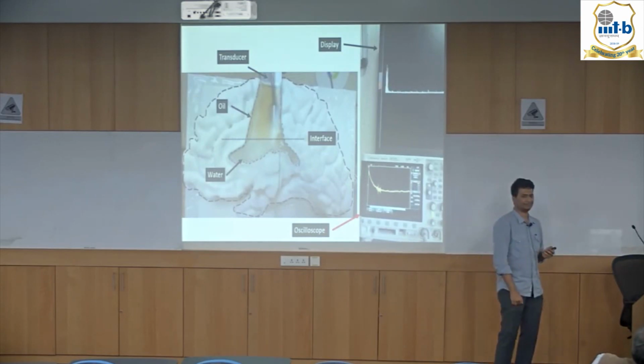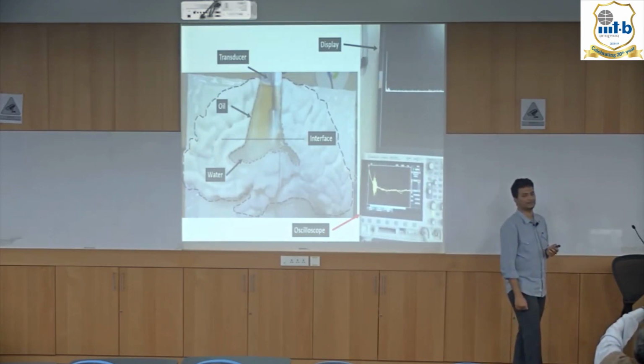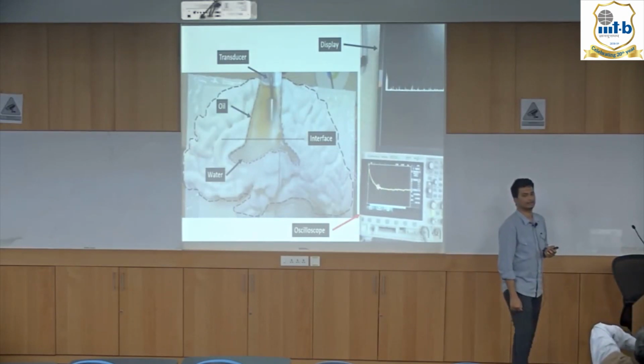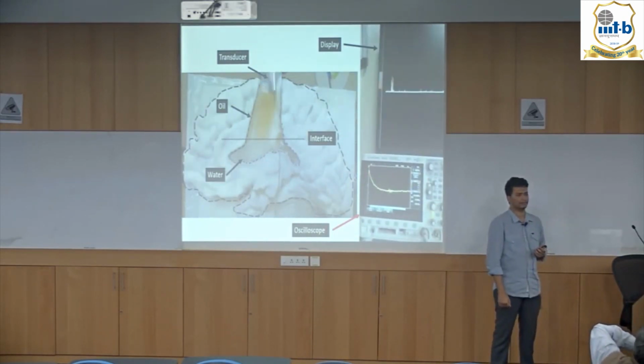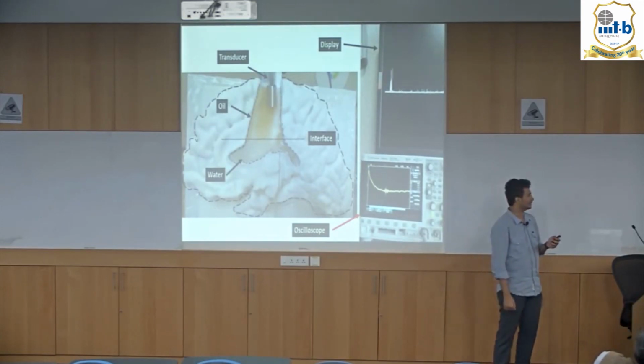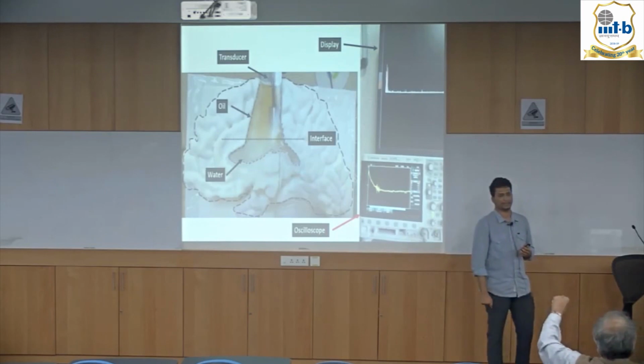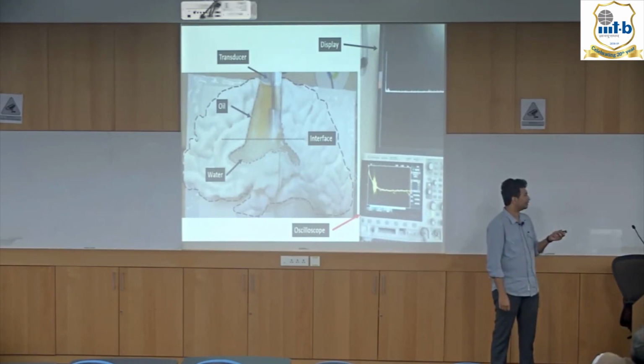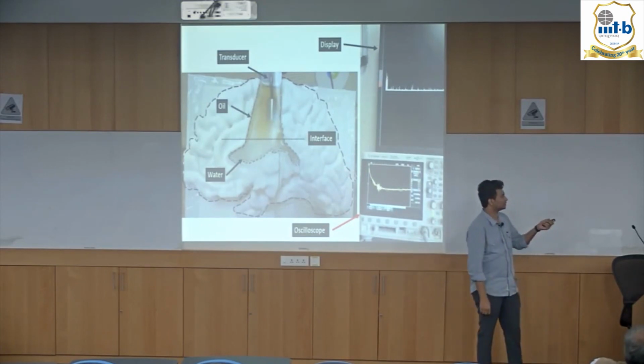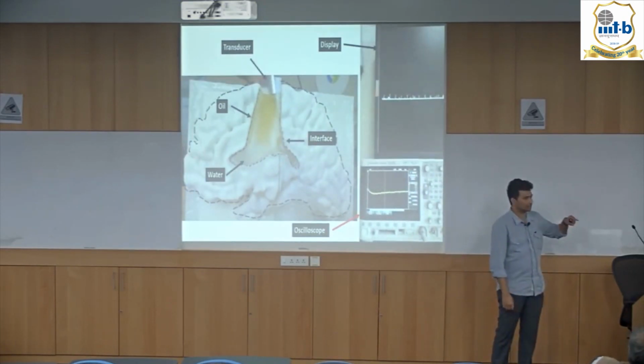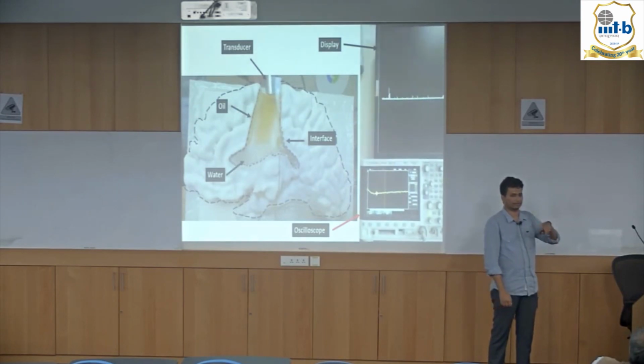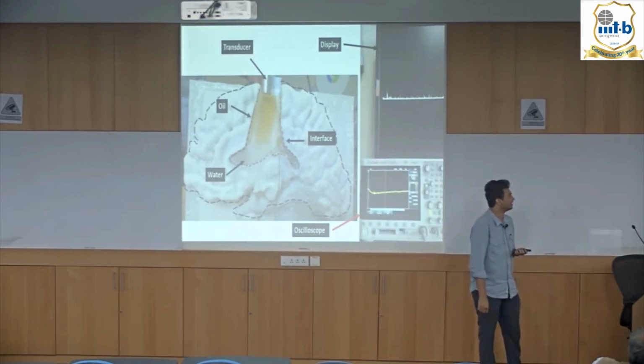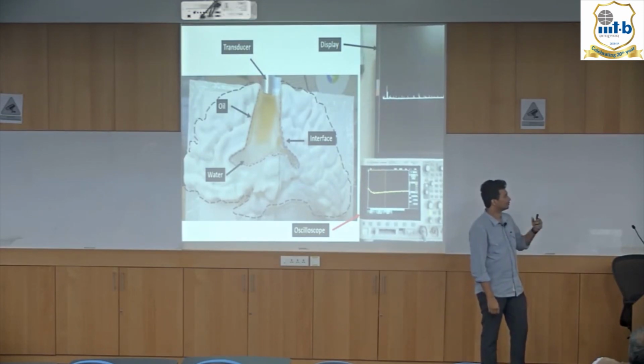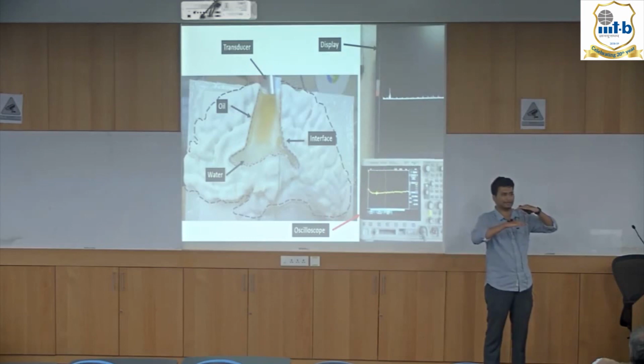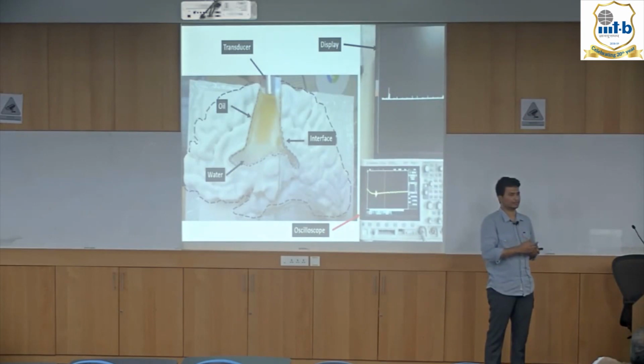You have to hold it steady and tight. We had made an arrangement, but okay, have it steady. There's another demonstration where the transducer is moved at an angle across a sector. Whenever the transducer's face comes parallel, or close to parallel, to the interface plane, there is an echo which can be captured.